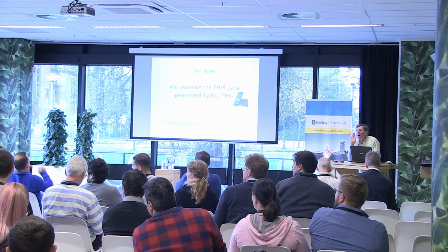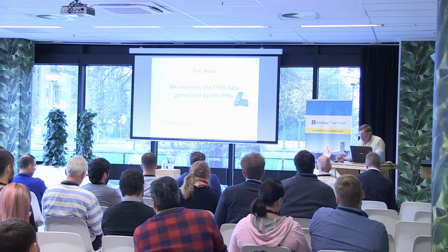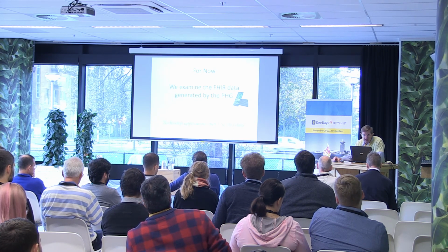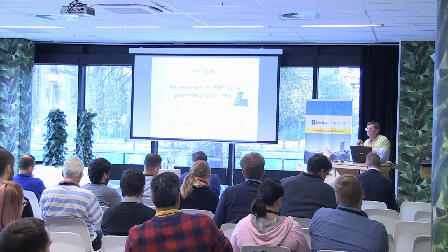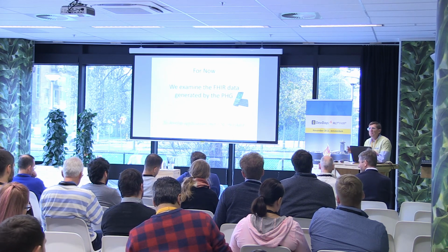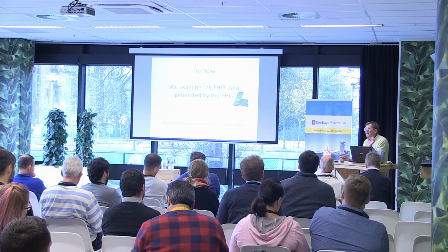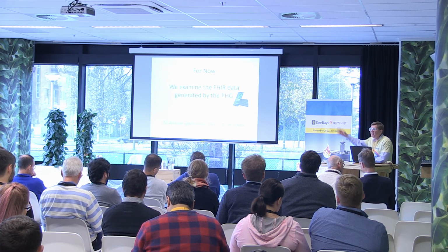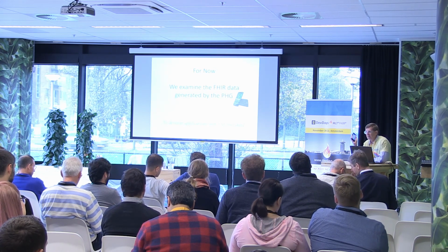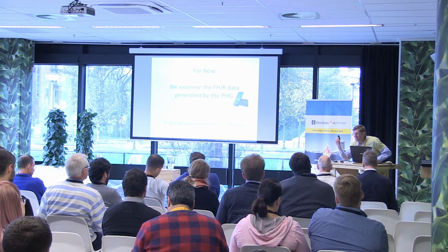Are there any devices that talk FHIR directly? No. That might happen in the future, but there's a problem: it's a lot more demanding on energy resources. The last thing people want are bigger devices that need more battery power, especially when you have to wear it. You want the smallest, least obtrusive thing possible that takes the least amount of power so your battery lasts as long as possible. FHIR is huge, and compared to the binary protocols it's hopelessly inefficient. You have one line in there that takes the whole binary string; you're talking bytes here, not kilobytes. That is a totally different order of magnitude. Clearly, if you have a sensor on something like this, which people are doing, you've got wireless, you've got cellular, but these are power consuming compared to something like this, which is a glucometer.